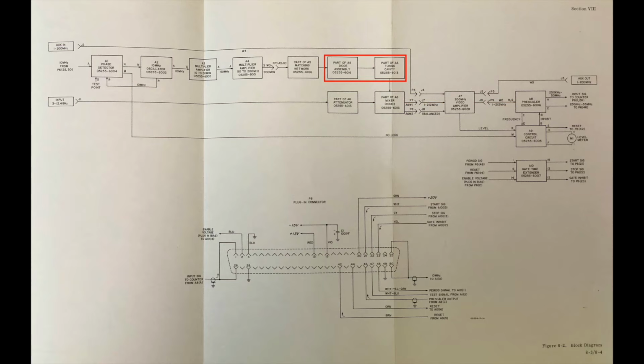Now the harmonic spectrum is created by a step recovery diode in the tunable cavity. The cavity is tuned to pick out a single harmonic of 200 MHz between 3 and 12.4 GHz in 200 MHz steps. The measured frequency is the dial indication plus the frequency counter display. Since the prescaler takes 1 to 200 MHz and divides it by 4, a ×4 gate time extender is used, which causes the 5245L to give a direct reading, not the divide by 4 reading.